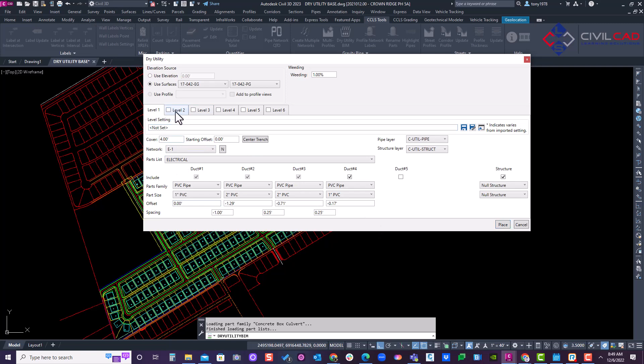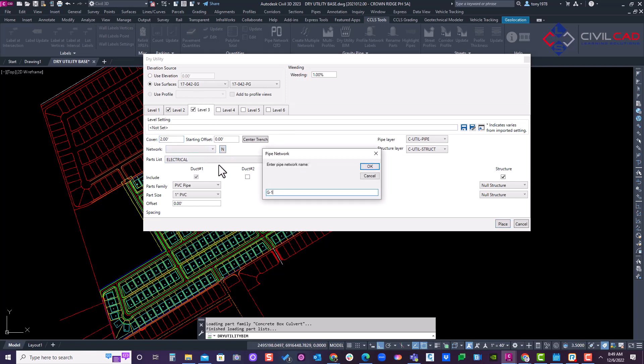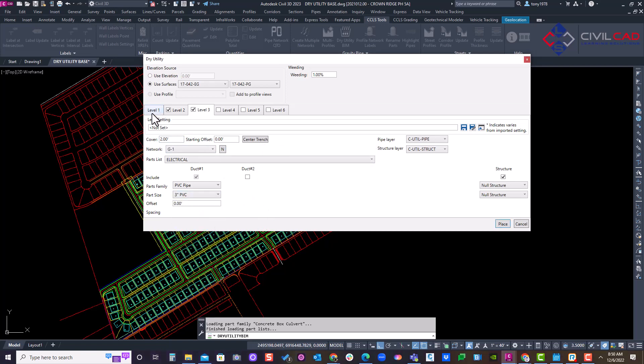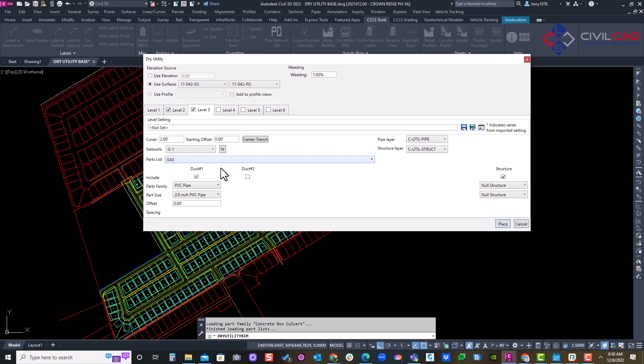We'll go to the third one — gas — and set it at two feet of cover. Give it a network name of G-1. It's a three-inch gas line. So we have four-foot electrical, three-foot fiber, and two-foot gas. The material is PVC, and there are other material types available as well. One gas line at two to three inches.